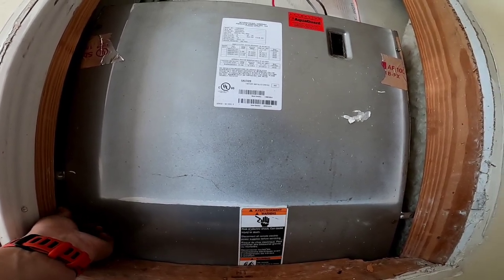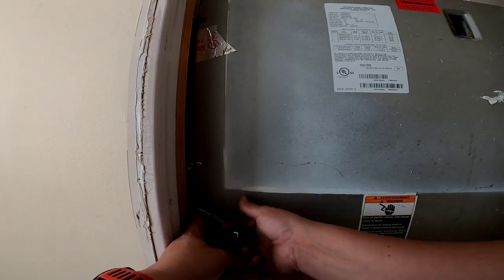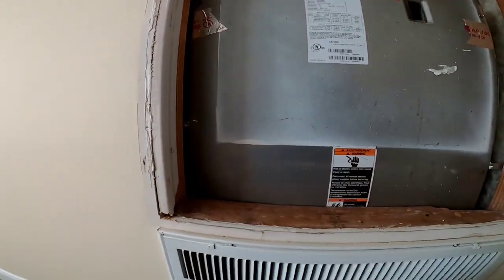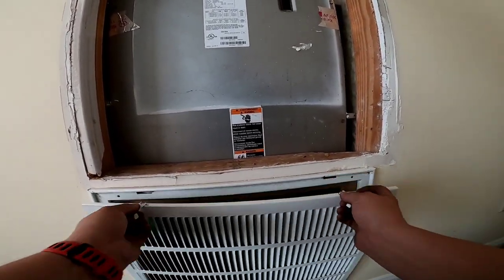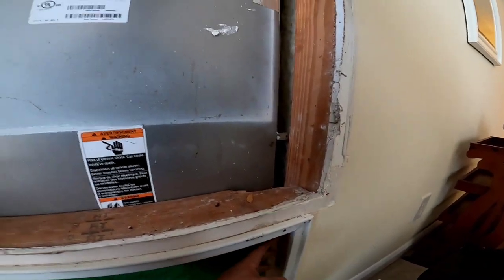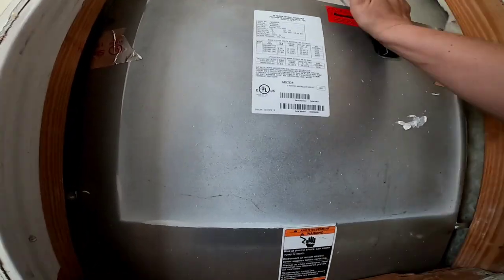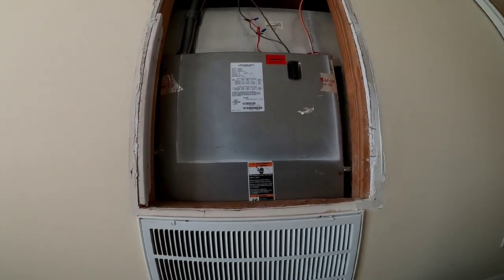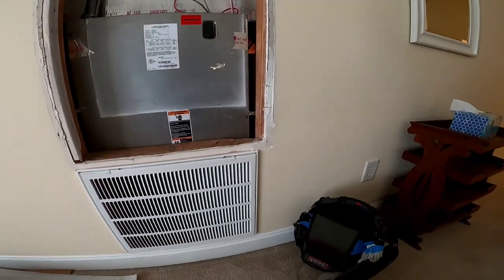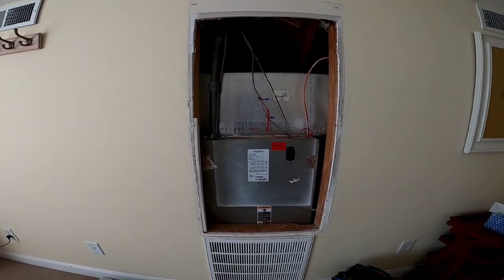This is a little bit different than what I would consider the ordinary blower motor change, especially around here. Apartments and things like that, you're going to see a lot more of these style units — I call them FF style units because I'm a Carrier dealer. The FF units basically have a free return, which is just a return grill. Pretty straightforward. We'll wait for it to come back on one more time, make sure no unusual noises, then put this cover back on and clean up. Hope you like this newer style video — if you guys like it I'll continue to make them, if you want me to go back to the old way just let me know. Thanks for watching, we'll see you on the next one.